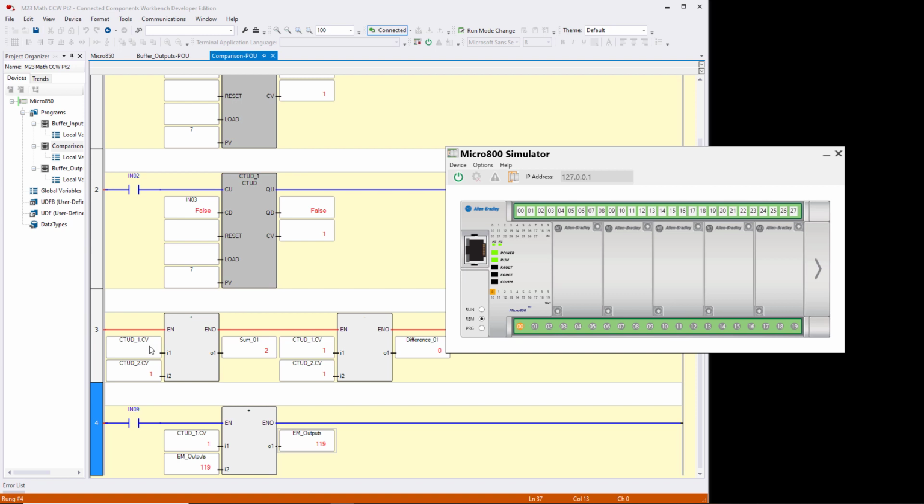The reason that this number doesn't start zooming up as a scan counter is because when it executes, it's adding these two values, and it executes this thousands of times a second. But the answer is always the same. This is 1 plus 119. So on the very first scan that this goes true, that's going to go to 120. The next scan, 121, 122, and so forth.